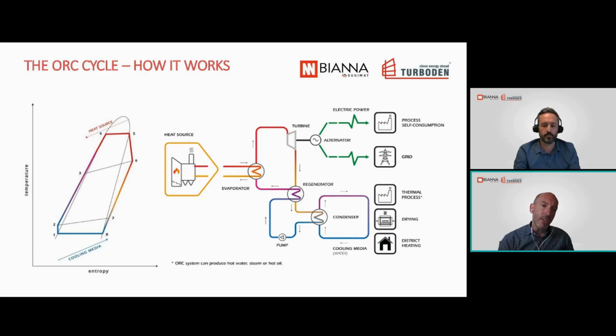What happens is the thermal oil coming from the boiler you have just seen, typically around 300 degrees Celsius, enters the ORC evaporator. Here, the heat is transferred to the working fluid, which vaporizes and expands through the turbine, generating electricity. After the turbine, the vapor passes through a regenerator first, where we recover some of the internal heat, and then it goes into the condenser where it's cooled down and turned back into liquid. Once it's condensed, the fluid is pumped back into the cycle and the process starts all over again.